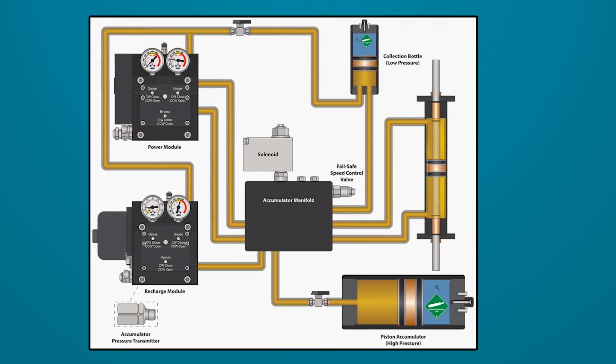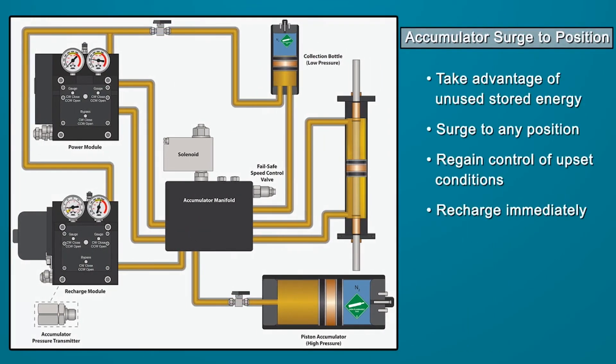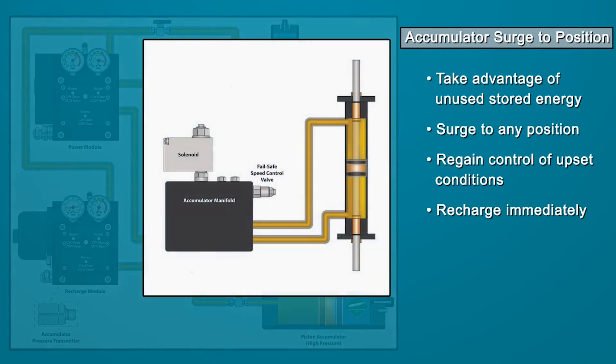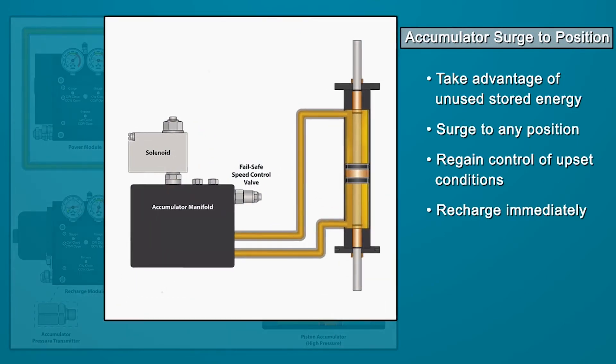Another benefit of the dedicated recharge module is the capability of performing two different functions with the same accumulator system. In addition to end-of-stroke fail-safe action, the accumulator can provide a surge to a target position by modulating the fail-safe solenoid.